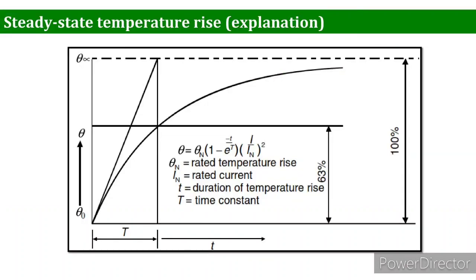So the first issue we have is the steady state temperature rises. In this case, as we know, in the interest of maximum efficiency, electrical machines should be loaded as close as possible to their permitted operating temperature limit. As we discussed in the last lecture also, if we exceed their permitted operating parameters, it will be very difficult to protect the motor from fault.